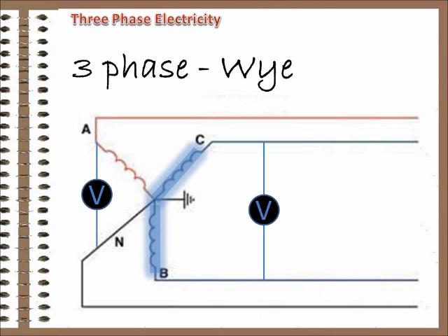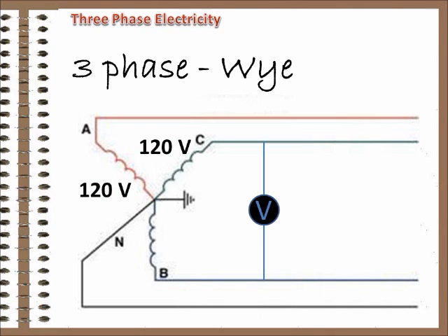Unfortunately, it's not as easy as multiplying by two because the phases are separated by 120 degrees, remember? For example, if the rotating magnetic field is creating 120 volts of potential in each phase, the combination of two phases results in 208 volts.